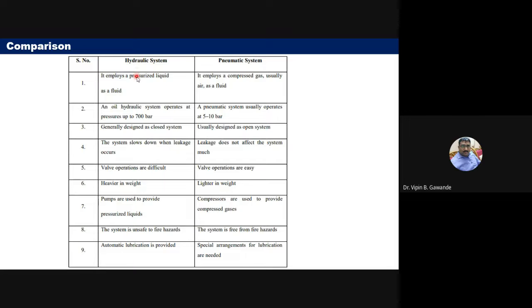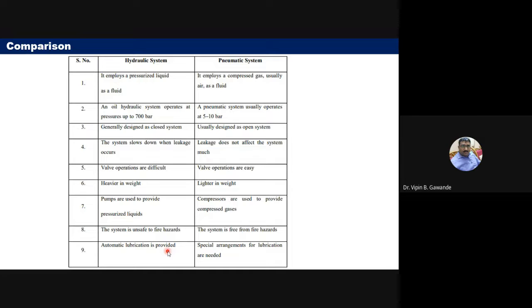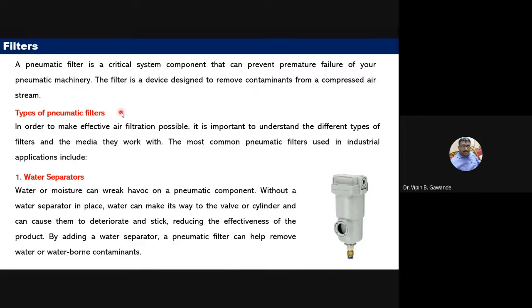In hydraulic systems, leakage causes the system to slow down, whereas leakage does not affect pneumatic systems as much. Valve operations are more difficult in hydraulic systems. Hydraulic systems are heavier; pneumatic systems are lighter. Hydraulic systems use pumps for pressurized liquid; pneumatic systems use compressors. Hydraulic systems are unsafe due to fire hazards from oil, while pneumatic systems are free from fire hazards. Special lubrication arrangements are needed in pneumatic systems.